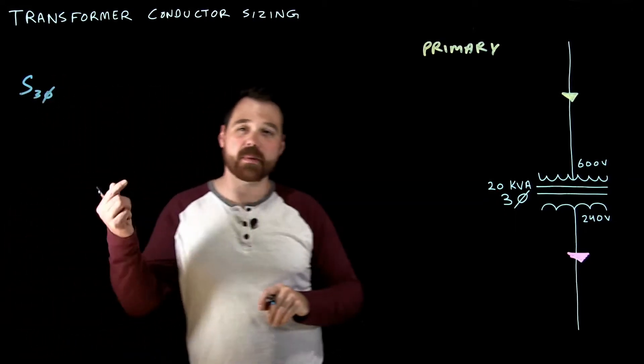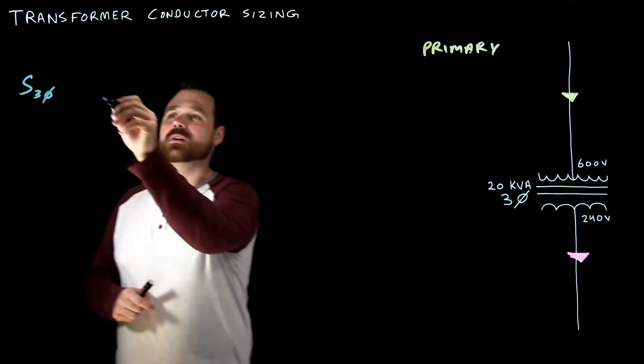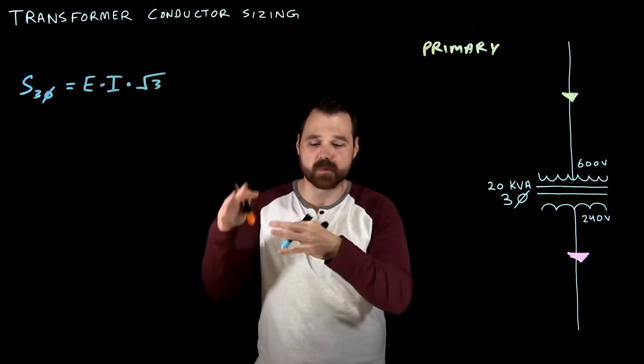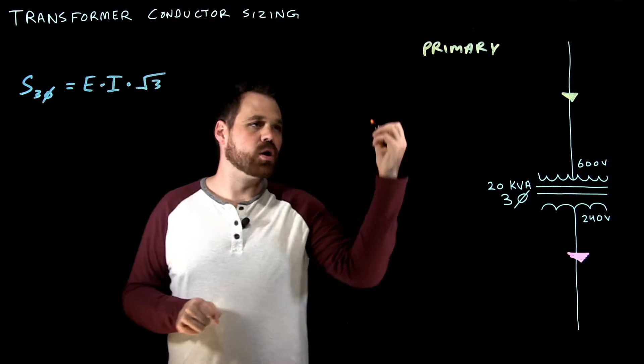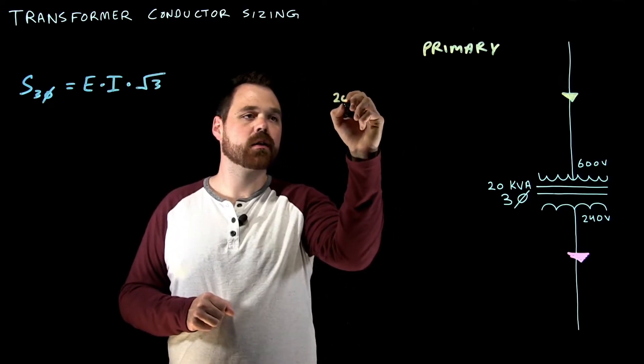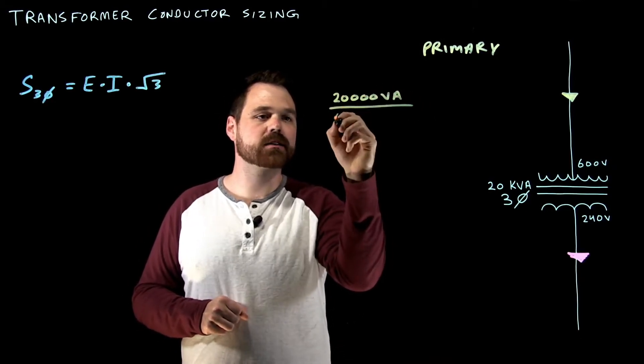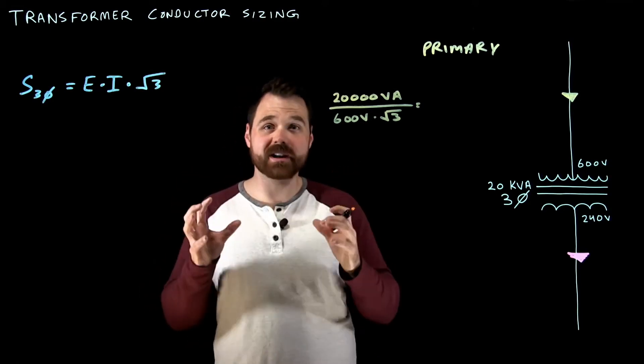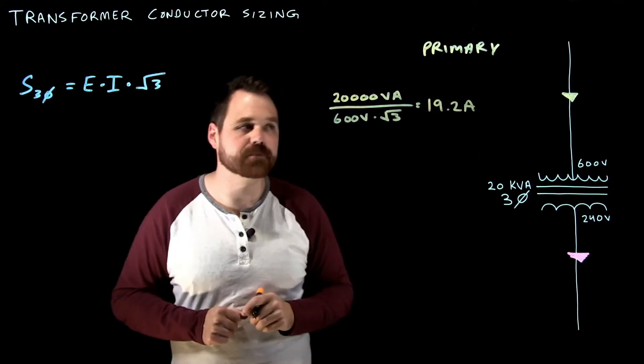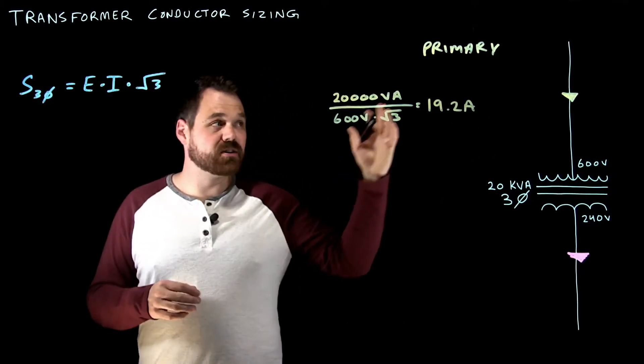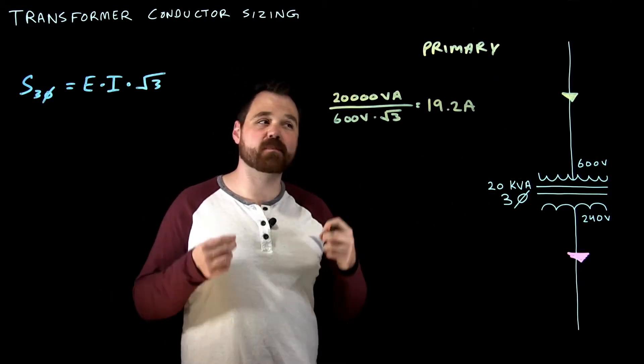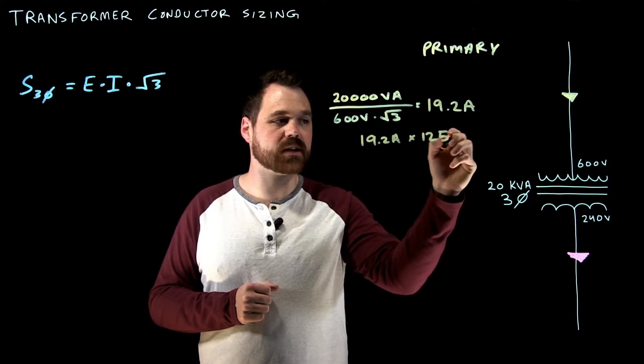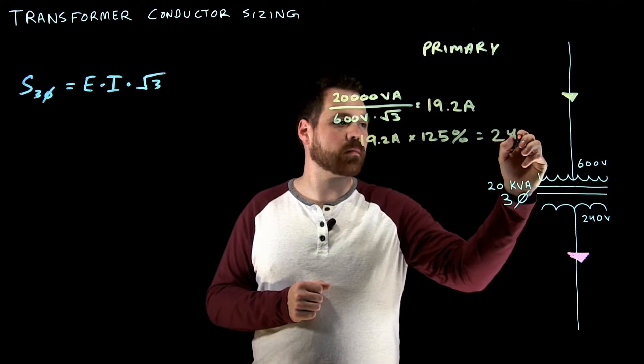We're going to use our S three phase formula, our apparent power for three phase, because we're talking a three phase transformer. We know that's E times I times root three. So we're going to use that formula transpose it. And that's how we're going to calculate our rated current in this case. So that would mean that we would take 20,000 VA divided by 600 volts times root three, that gives us a rated current, the rated primary current of 19.2 amps. Now, we need that conductor to actually be able to carry 125% the rated current. So we're going to take our 19.2 times 125% and that is going to equal 24 amps.